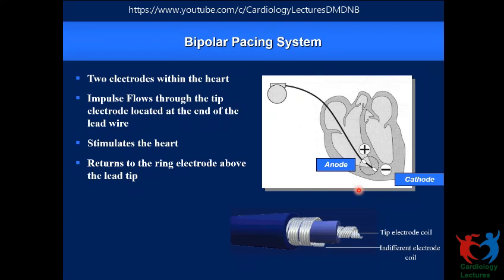And the modern pacemakers are capable of measuring impedance constantly while it's pacing. And if there is a fracture that happens, we will discuss that in greater detail, but I'm sure you know this, there is going to be an impedance change that might go out of range. And the pacemaker itself automatically converts itself into a unipolar configuration. And when the patient comes for a regular follow-up, he would not know that because he's not going to be symptomatic, but the programmer home screen will pop up a warning stating that there was a polarity change because of a suspected lead issue because of lead impedance. And you may want to investigate more thoroughly. And if it is a true impedance change because of a lead fracture, then you may ultimately want to change the lead for that patient. So that's the advantage of the bipolar system as it exists today.